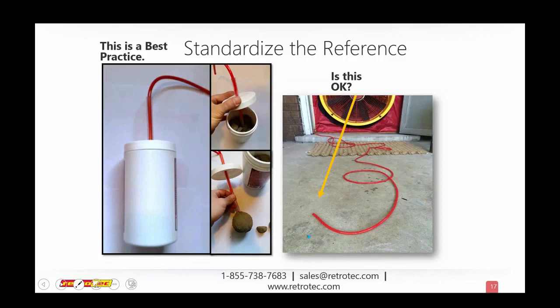Let's see. So, any questions here, Joe, that you want to talk about? No, I do want to have one. Yeah, go ahead. On the picture you showed, I picked on you last time when you showed this picture, but you show the tube elevated in the air and hanging from the hand railing. When that happens, that tube will oscillate back and forth and create quite a bit of pressure, even if there's not very much wind. You can figure that out yourself just by taking the tube and waving it back and forth while it's attached to the gauge, and you can see that. So it's always important that the tube is in a stable position so that the tube itself is not moving, because when it does, the flexing of the tube will create pressure.